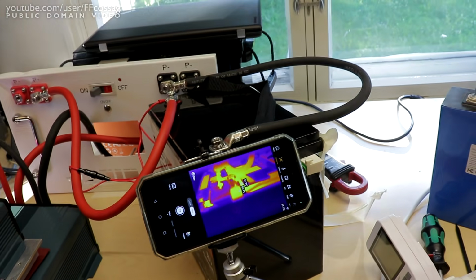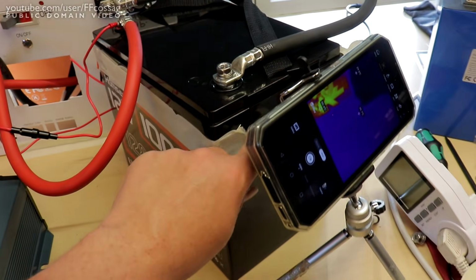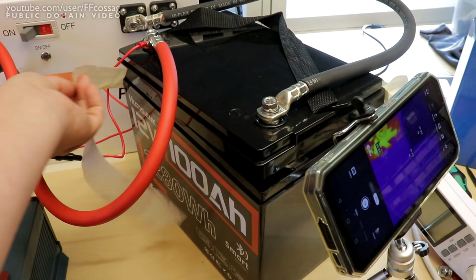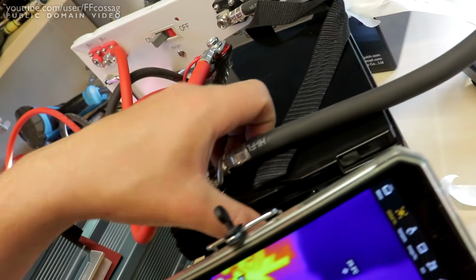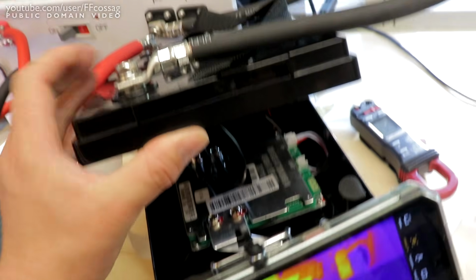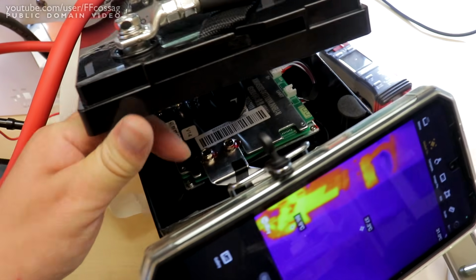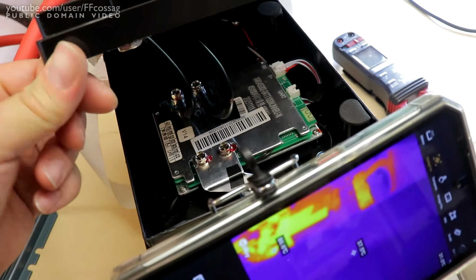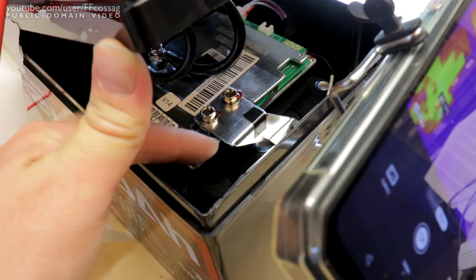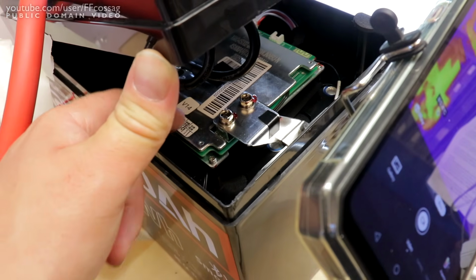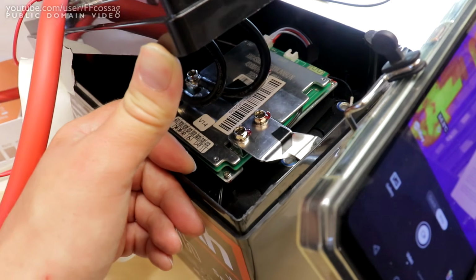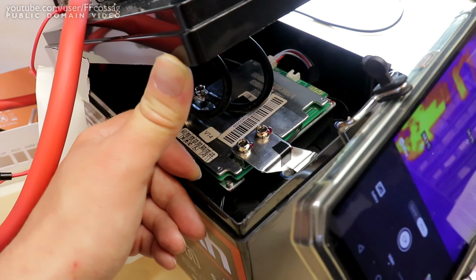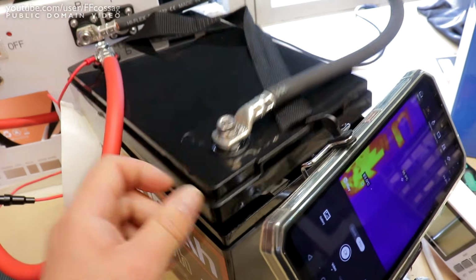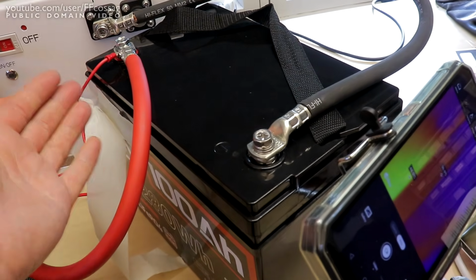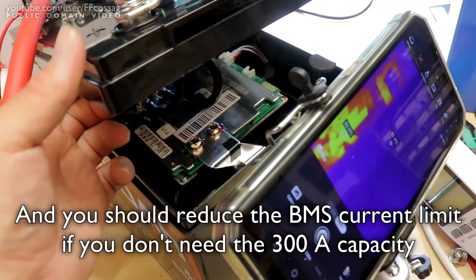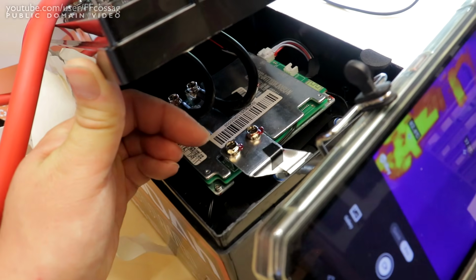It's as I expected. It's just really hard, given the thermal configuration of this battery. Even though it does get really toasty, like everything here is hot to the touch, and if I were to touch any of that stuff I would get burnt. But the fact that the bus bar has such a good thermal connection to the BMS just makes it trip the BMS before anything really has time to get super toasty. This is a 100 amp rated battery, you should still have this fused at about 100 amps. But for peak powers, it's not going to self-destruct even if you do abuse it.